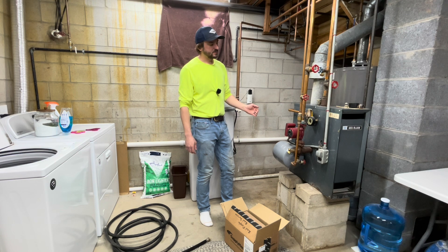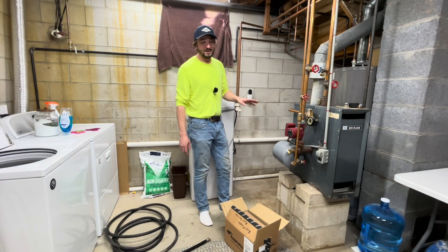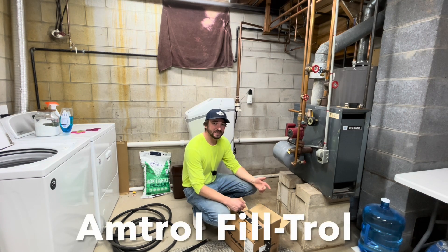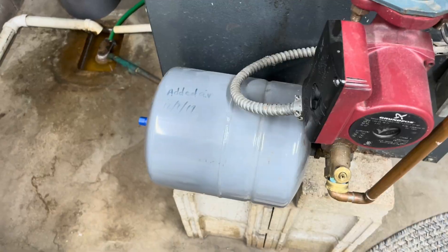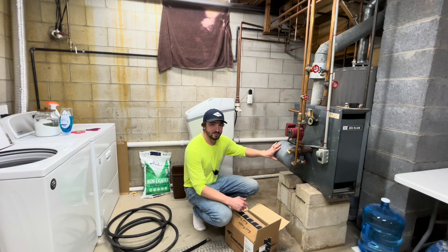One problem I'm noticing is the pressure gauge is reading right around four or five PSI — I'd like to get that a little bit higher. This new expansion tank comes pre-charged at 12 PSI. I reached out to Amtrol today regarding their Fill-Trol down here; this is the older style. I was able to talk to someone on the phone who was aware of the horizontal mounted expansion tank. He said nowadays they're putting expansion tanks mounted vertically, which is better for the diaphragm, but I could still mount mine horizontally knowing it may reduce the lifespan.